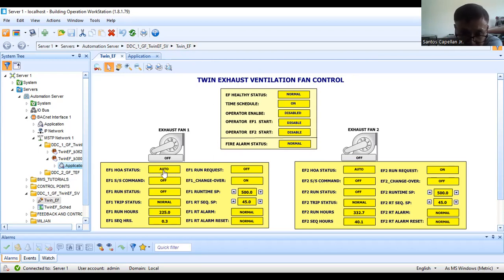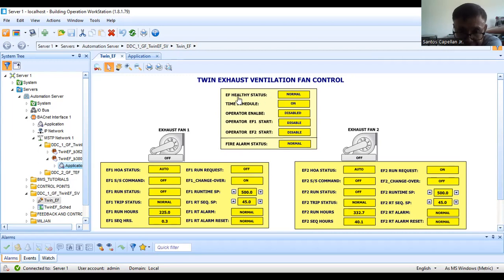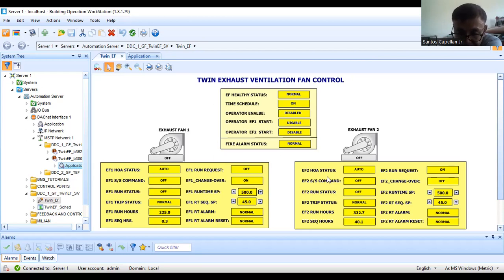As you can see now, our selector switch is in auto. EF1 auto. I have here EF health status. This will tell the operator that the system is healthy if there is no trip in any of the fans and there is no manual position for the selector switch of any of the fans.